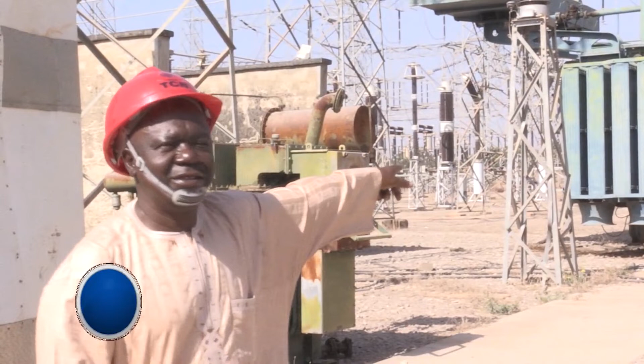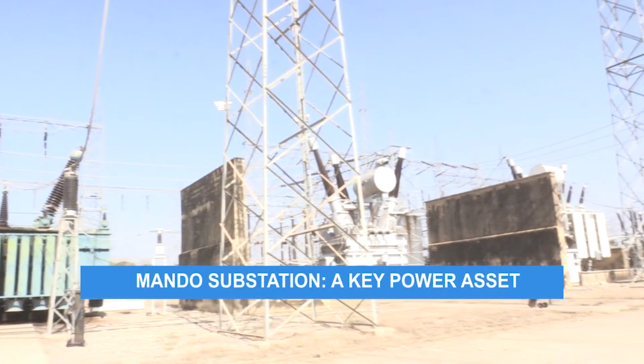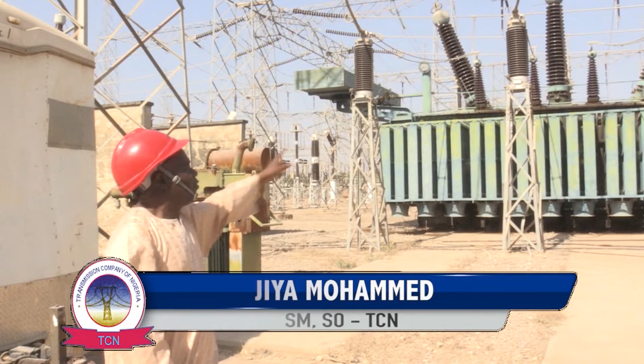As you rightly know, we operate at N-1 redundancy. This transformer is on soak, meaning it is not loaded to the consumer. It can only come in if we need to carry out maintenance on one of our transformers here, so we don't transport the load and keep other people in darkness. Since we have redundancy, we have continuity. We load the transformer and feed the other consumer. After completion of the job, we transport the load back from the 90 MVA to the 150 transformer for continuity of supply to the consumers.